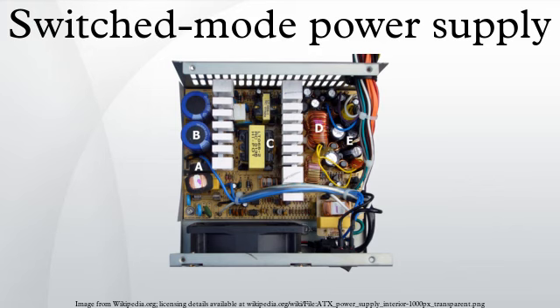Such SMPSs draw current from the AC line in short pulses when the mains instantaneous voltage exceeds the voltage across this capacitor. During the remaining portion of the AC cycle, the capacitor provides energy to the power supply. As a result, the input current of such basic switched-mode power supplies has high harmonic content and relatively low power factor. This creates extra load on utility lines, increases heating of building wiring, the utility transformers, and standard AC electric motors, and may cause stability problems in some applications such as in emergency generator systems or aircraft generators.